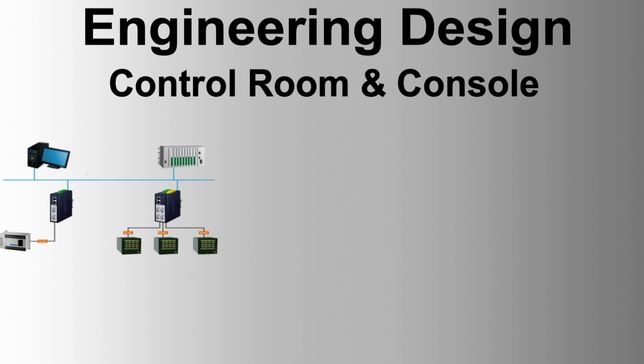Workplaces in the control room should be equipped for administrative work, checking of drawings, meetings, etc. The furnishing of these workplaces should take account of their functions. Visual partitions should be present between various workplaces, with the console visible at all times. Workplaces should not be located near ventilation grids. In small control rooms, measures should be taken to avoid a shut-in feeling, e.g., vertical glass strips, windows, wall decoration. In large control rooms, measures should be taken to reduce noise levels and enhance speech audibility. Computers and peripherals, due to noise and heat, should be installed in a separate area as far as possible.